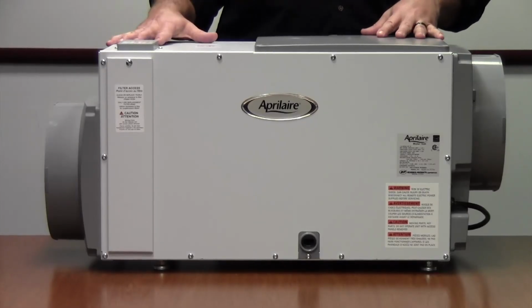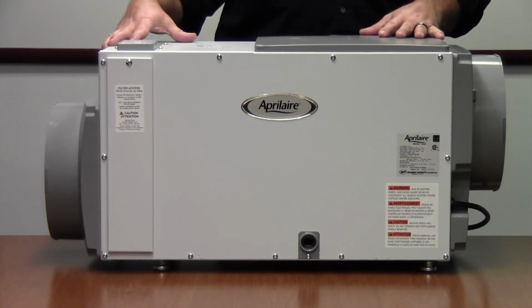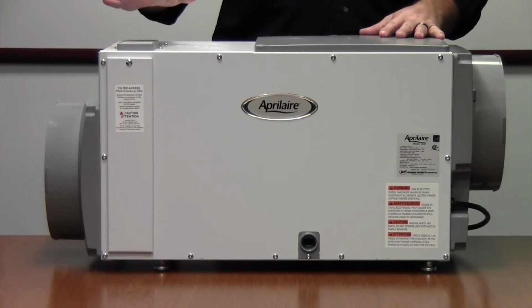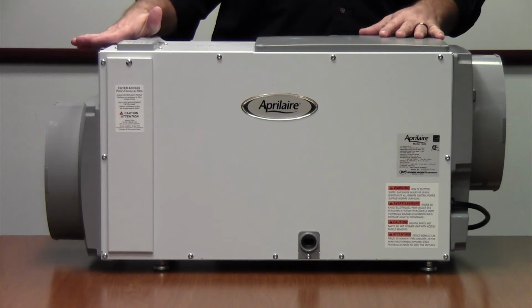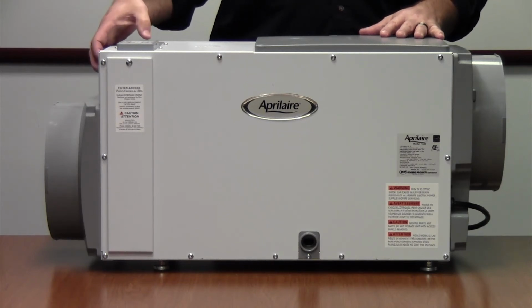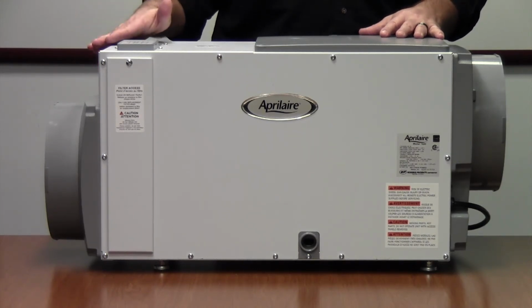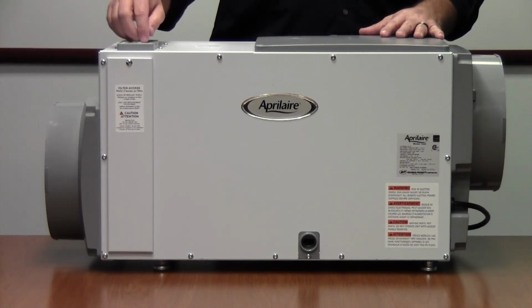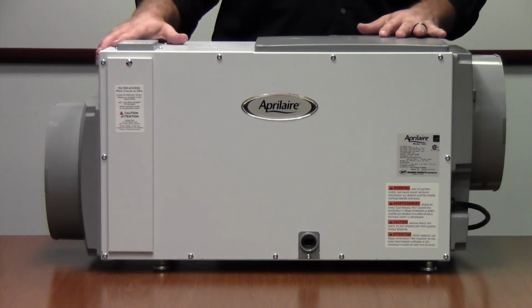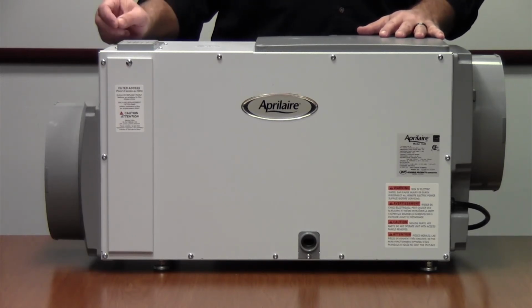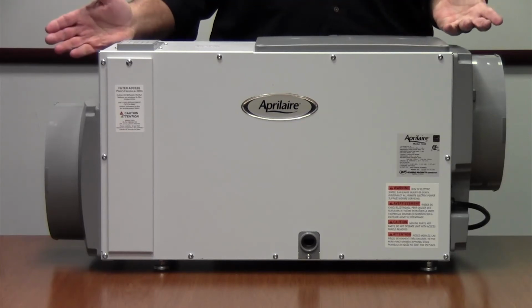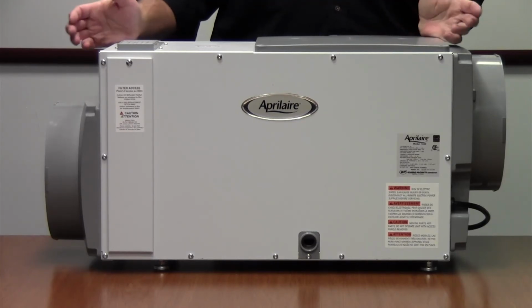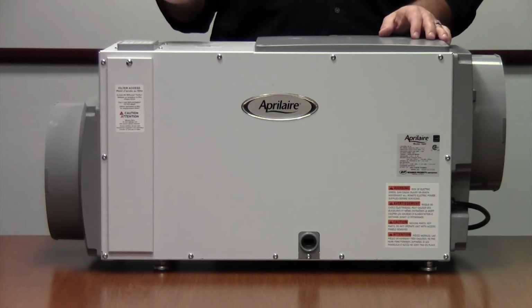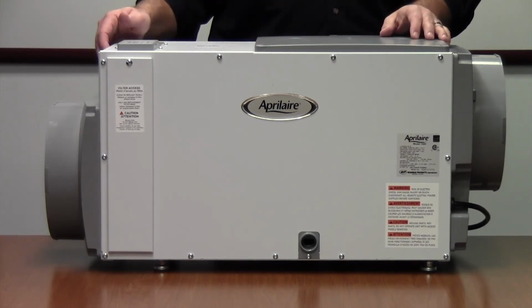Alright, once you get the unit completely installed and we want to turn the unit on, anytime you turn the unit on when we're using the internal control, it's going to take an air sample, or any time that you increase the set point, it'll take an automatic air sample. Our sensor is inside underneath this cover, so we have to measure the air coming through. So we turn the unit on just like our other units for 3 minutes to sample that air. And at the end of 3 minutes, we decide yes, we need to have dehumidification, or no, we don't. So we'll turn the compressor on, or we'll shut off, and then every hour we'll continue to sample until we do need to run.